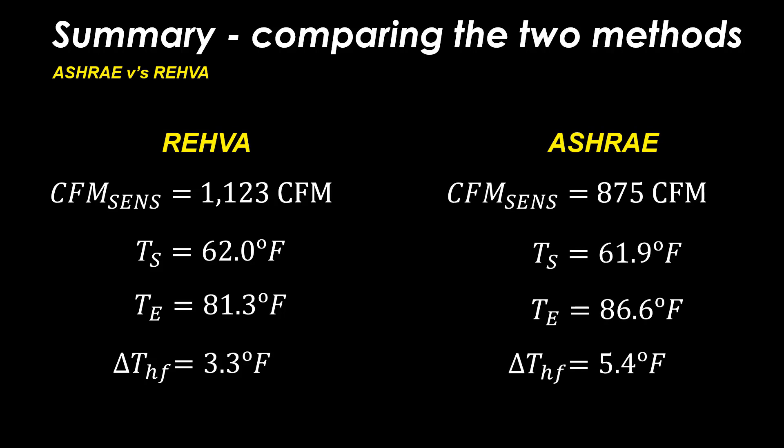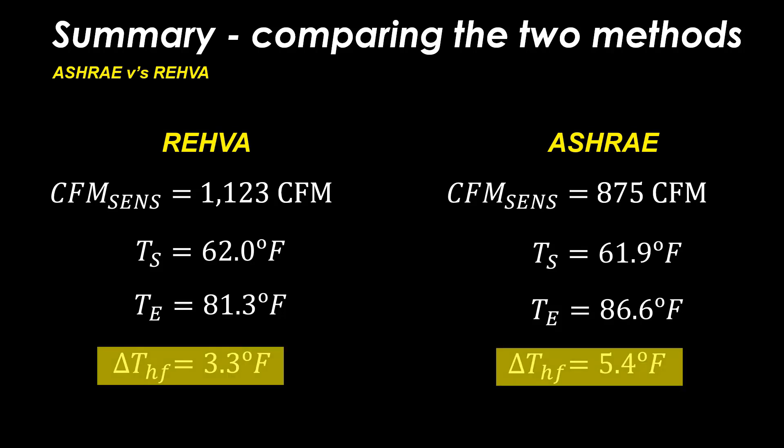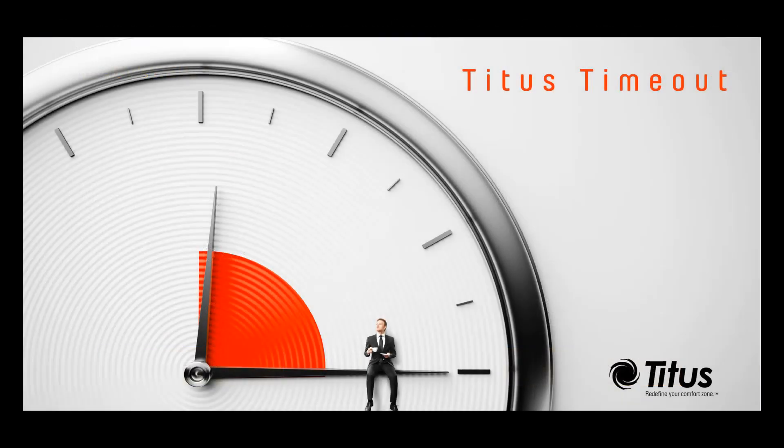Clearly, the REHVA method is more conservative, particularly as the floor to head delta T is only 3.3°F compared to the 5.4°F in the ASHRAE calculations. So that about wraps up the demo of the REHVA method.